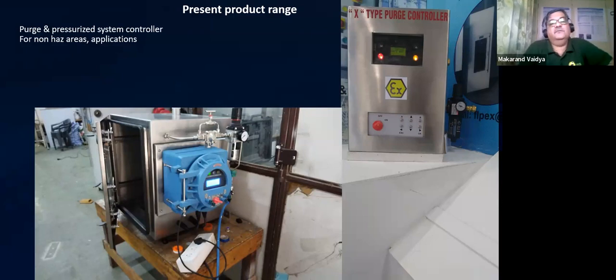So those things we can deal with through purging and pressurizing. Purging and pressurizing, those two words themselves are sufficient to understand: first you purge out the stale air inside the control panel, then you pressurize it to a positive pressure, more than the ambient around, so that there is no contamination.